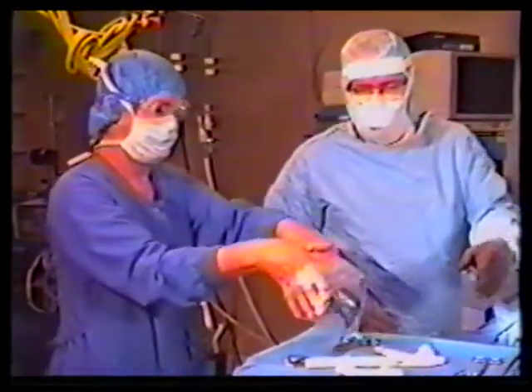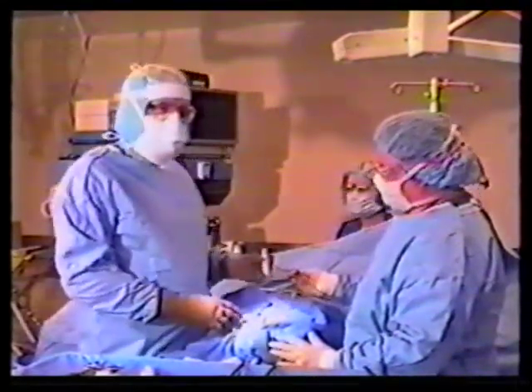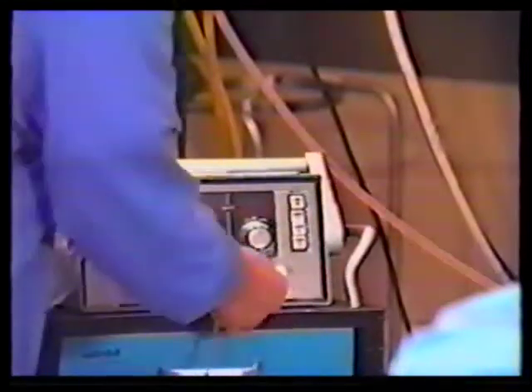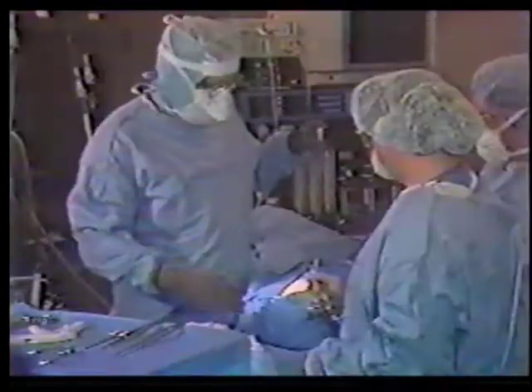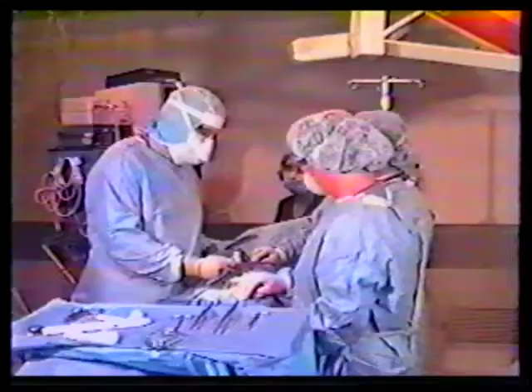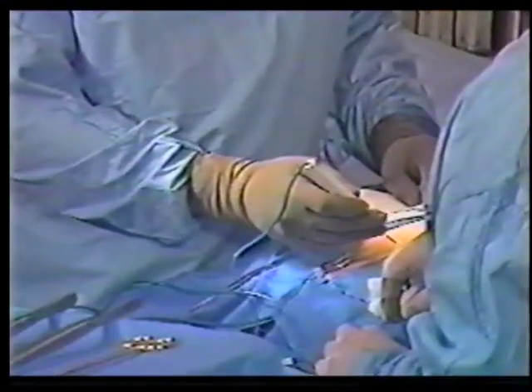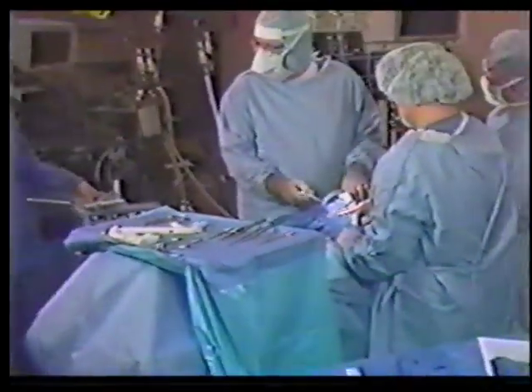Now, how about trying a new Bovie first? All right. Suffering succotash. Jeez, oh, darn it. Captain Billy's whiz bag, it's not working. Let me change the machine. Okay, try it now. It's working great. What in tarnation was wrong with that other machine? I don't know. I'll fill out a faulty medical device form, and include the original Bovie with it, give it to the biomed tech, and he'll see what he can find out. Good.